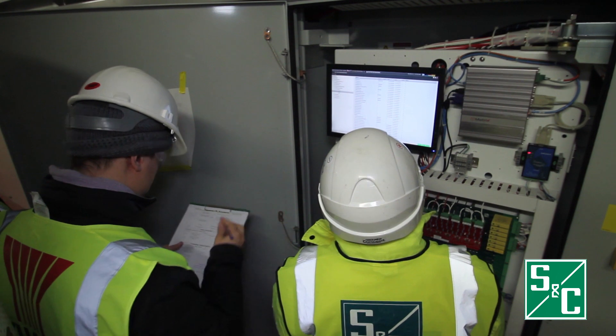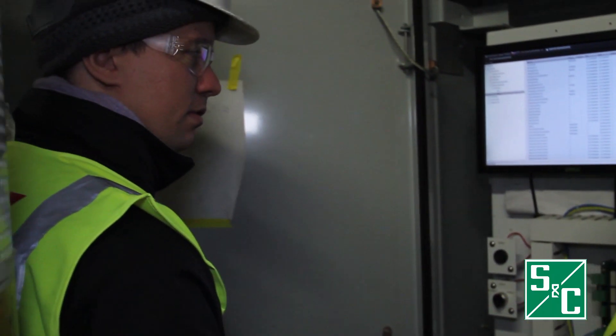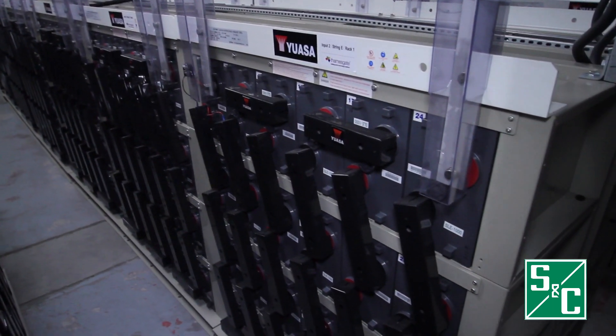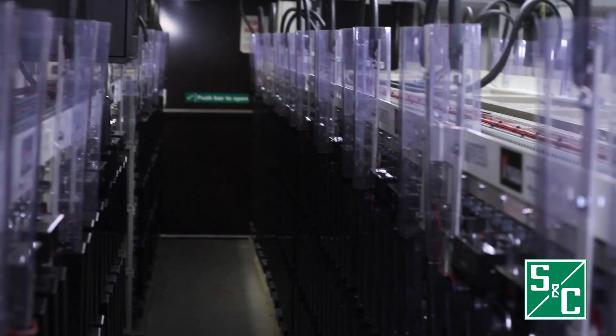The total we're looking at here is 3 megawatt hours of AC output power. These batteries have been chosen particularly for their ability to cycle. Although they are lead acid batteries, these are valve regulated lead acid batteries which are designed to be gas recombining inside them.